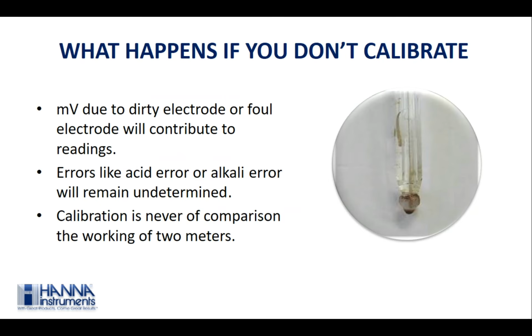But what if you don't calibrate your electrode? If you don't calibrate your electrode, errors due to many factors will contribute to your reading. It might be due to deposition or due to a dried pH electrode. The millivolt generation by the deposition on the electrode will add on to the millivolts of the buffers or samples, thus leading to a higher reading. Other than this, errors like acid error or alkali errors will remain completely unidentified.